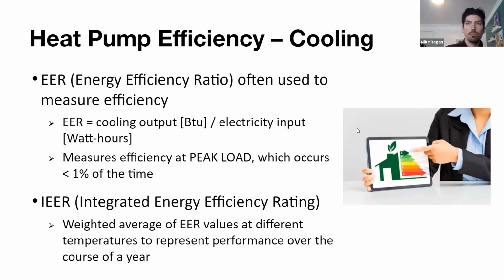So we're talking about efficiency when we're talking about the advantages of the inverter-driven compressor. When we're talking about cooling efficiency, there are a number of metrics that we use to assess energy efficiency. One thing we utilize is EER, or energy efficiency ratio. It's a very simple formula where you measure the cooling output in BTUs against the total electricity in watt hours that you're putting into the system. BTUs are a unit of energy, and electricity input is a measure of energy. By using that, you're going to figure out what your ratio of output to input is at a given time. But this one measures the efficiency at a peak load situation. So it's going to measure your total cooling output at the absolute max cooling load necessary.